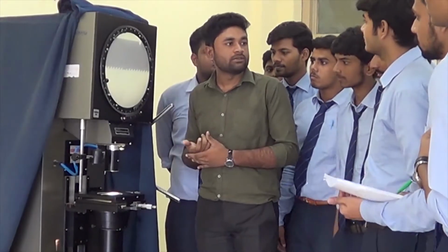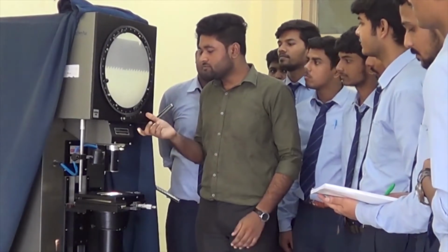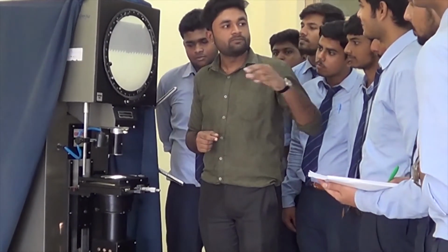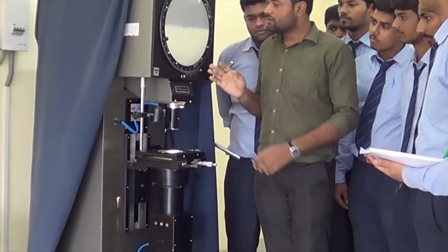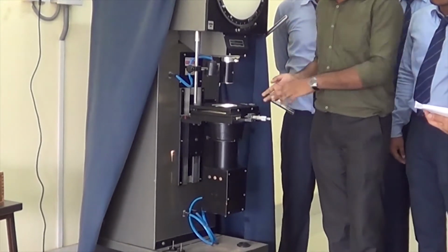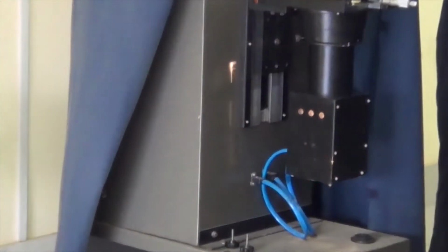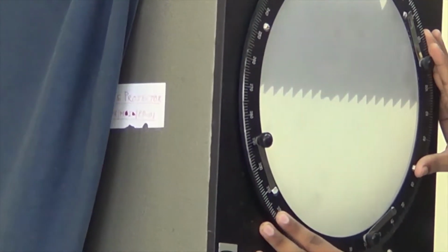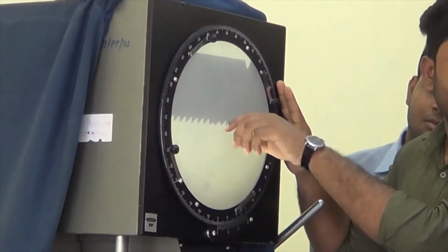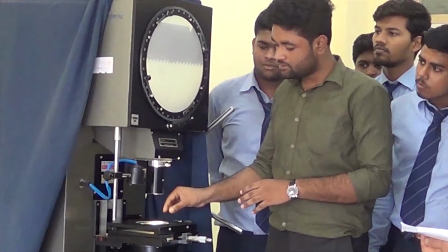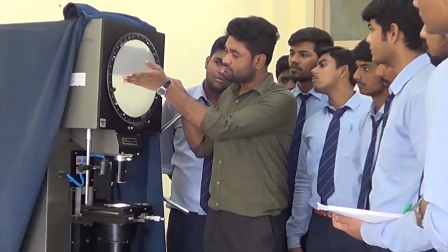Out of various interesting equipment and instruments used in our metrology and measurement laboratory, the profile projector is an advanced piece of equipment. A profile projector is also referred to as an optical comparator or even known as a shadowgraph. It is an optical instrument utilized for measuring. The projector magnifies the profile of the specimen and shows this on the built-in projection screen. On this screen, there is usually a grid that can be rotated 360 degrees.